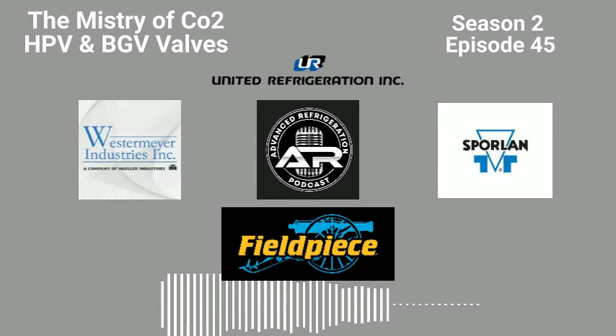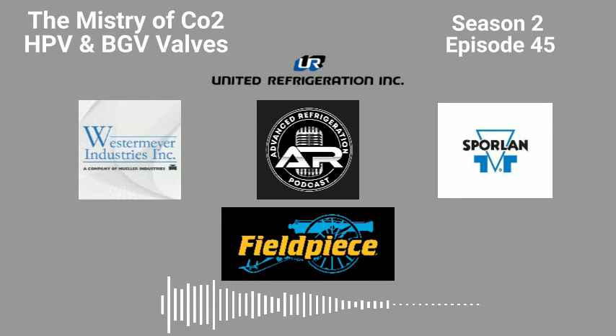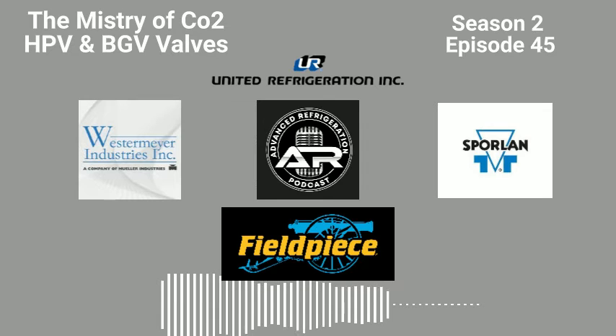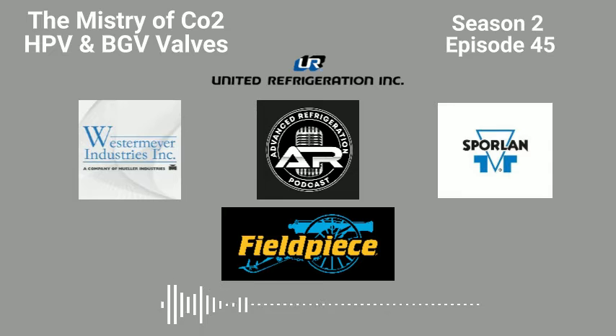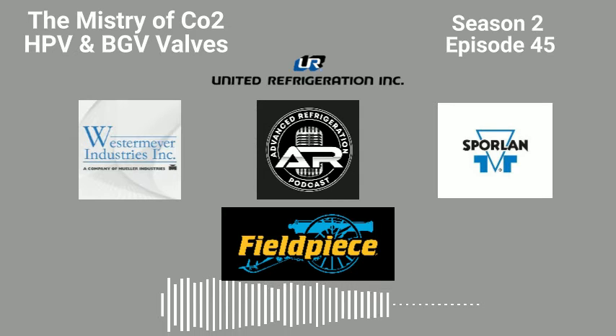So what they're doing is they're trying to maintain a subcooling number, a magic made-up number, on this condenser / gas cooler, because it's a gas cooler now, because all we're doing is rejecting heat. And they're trying to maintain this magic subcool number to keep this condenser running efficiently and at the same time not trip on high head, but also reduce the pressure in the receiver. So this valve does this balancing act.